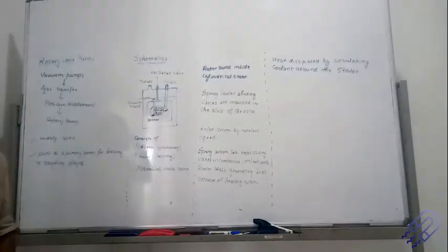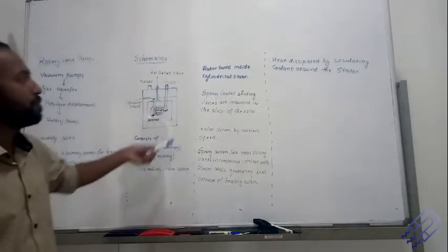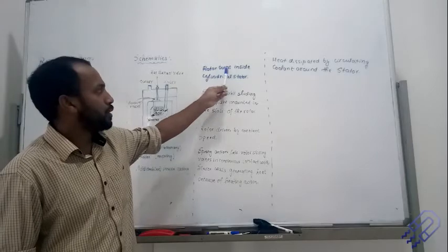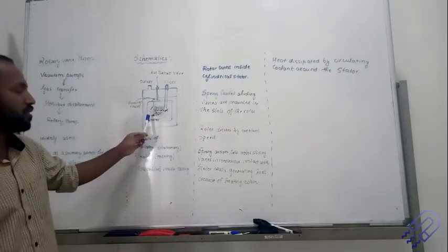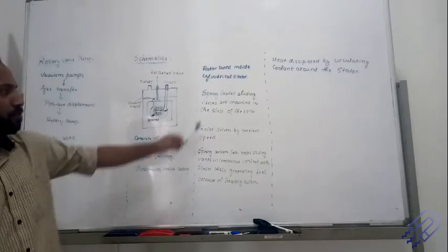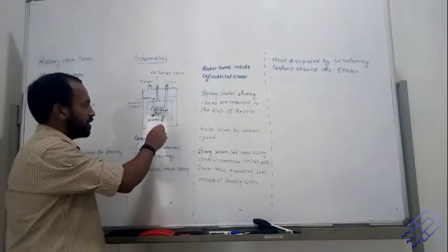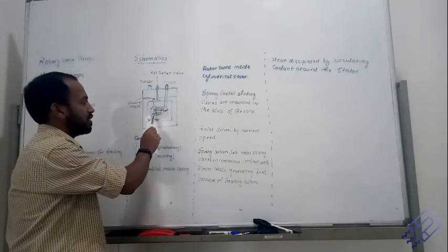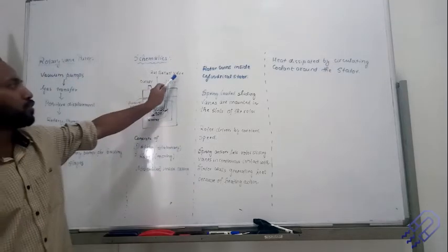When a rotary pump starts, the motor moves and you will always keep hearing the sound of the motor. The rotor turns inside the cylindrical stator — the stator remains fixed and the rotor keeps moving. Spring-loaded sliding vanes are mounted on the slots of the rotor.